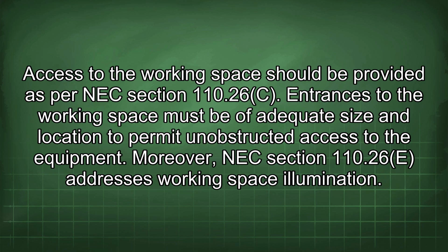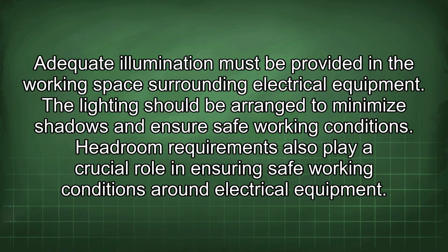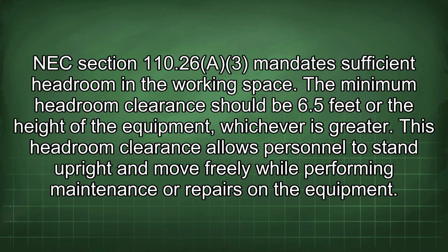Moreover, NEC Section 110.26(D) addresses working space illumination. Adequate illumination must be provided in the working space surrounding electrical equipment. The lighting should be arranged to minimize shadows and ensure safe working conditions. Headroom requirements also play a crucial role in ensuring safe working conditions around electrical equipment. NEC Section 110.26(A)(3) mandates sufficient headroom in the working space. The minimum headroom clearance should be 6.5 feet or the height of the equipment, whichever is greater.